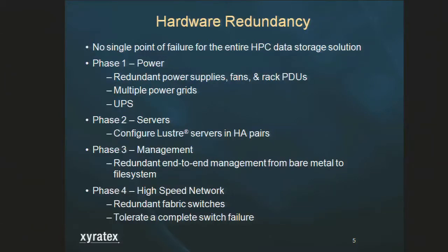And secondly, power outages: you could try to build a solution and avoid power outages as much as you can, but UPSs are still critical to protect certain aspects of a storage subsystem. It could be protecting the metadata and management functionality, so those services will stay up and gracefully shut down if the power outage exceeds the battery life of a UPS. So you could gracefully bring those systems back up and then bring up the rest of the service cleanly, without having a storage subsystem crash uncleanly during an unexpected power outage or power glitch. So UPSs and targeted UPS protection is critical.